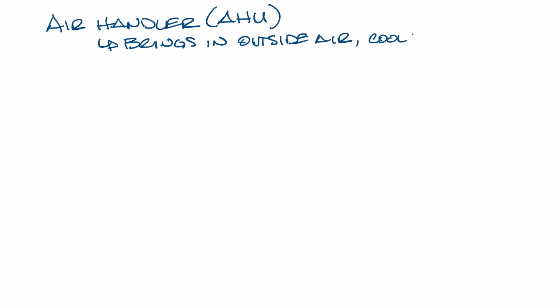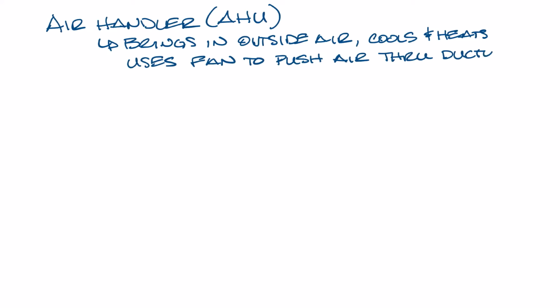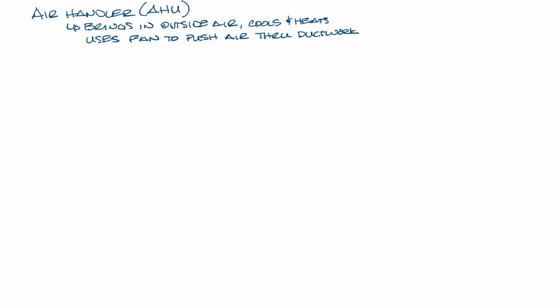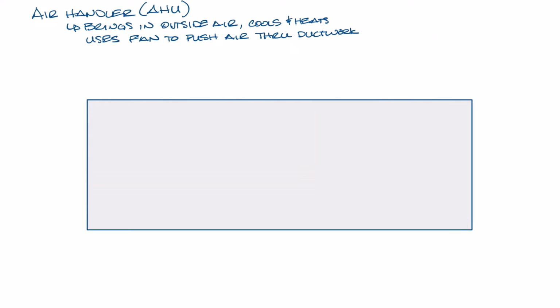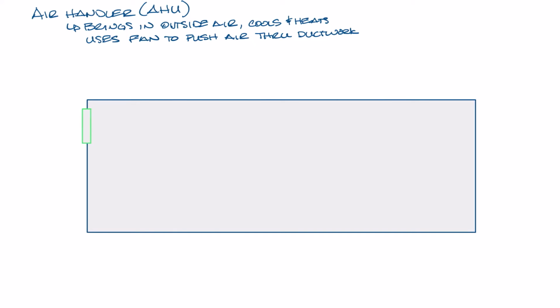So an air handler is a piece of HVAC equipment that, at minimal, brings in outside air, cools or heats it, and uses a fan to move it through the ductwork in the building. From there it would go through the VAV boxes, out the diffusers, and into the occupied space. So let's make a little room here and draw this. So we'll start with the cabinet, and then let's put a damper here.